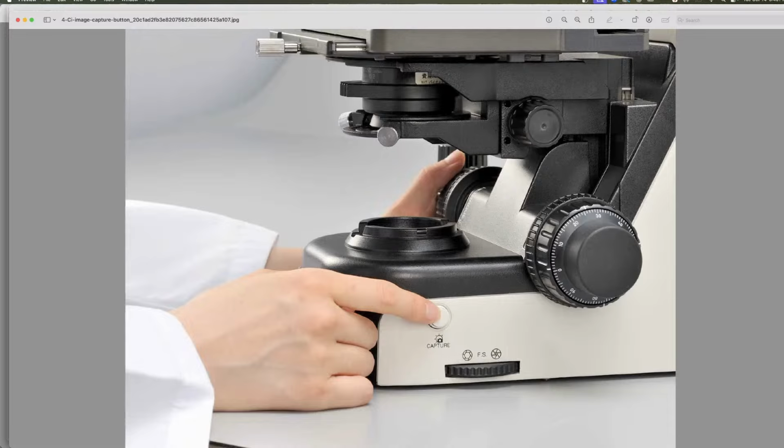Now, Koehler illumination is a way that you can ensure that every single point on your specimen is illuminated the same way, by light that is coming from all directions but equally, and that is the only way to get an image that is completely free of imperfections in the light source.